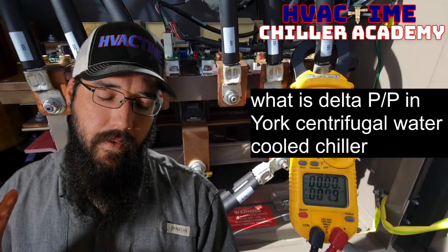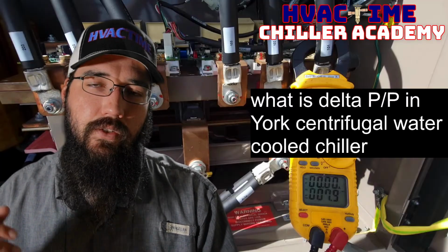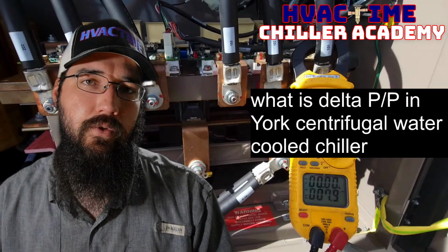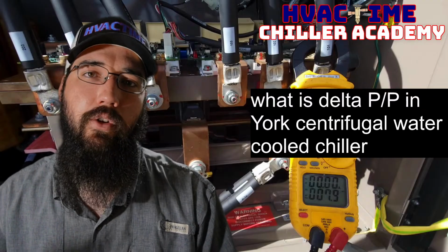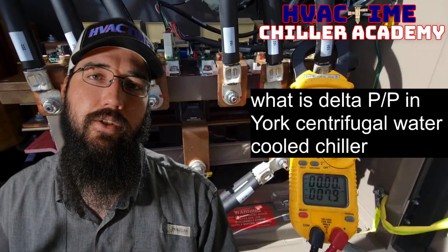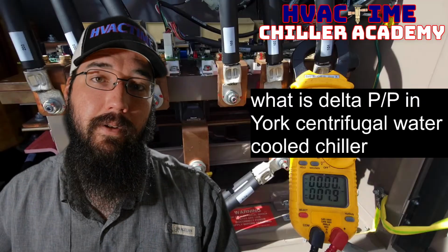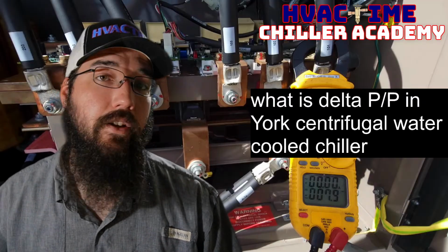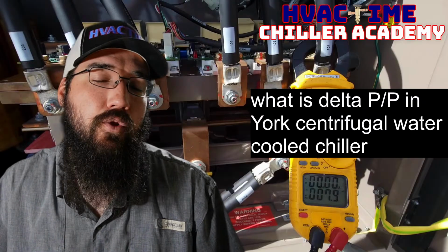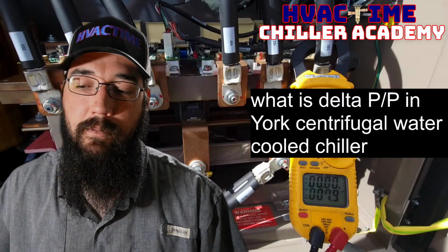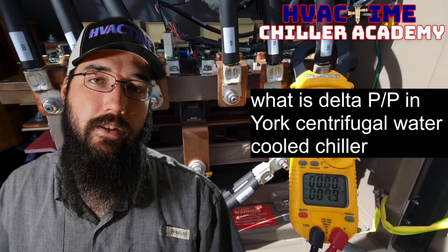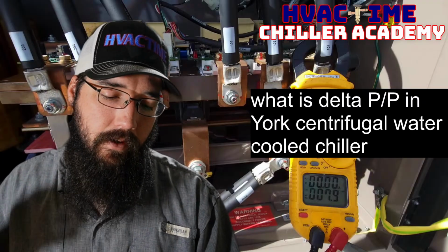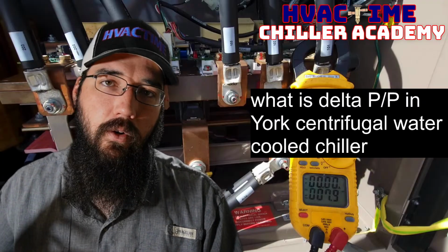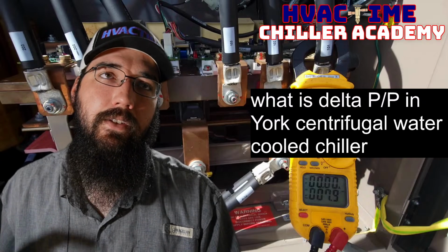Either way, in that case, as soon as you've got that condenser water problem resolved, then if it took a minute to get it resolved and the chiller still had to run during the meantime, which, I mean, while it's not ideal, these things happen. We can't control all the conditions at our plant. Sometimes we just got to get the chiller to grunt through it. It's unfortunate, but true.